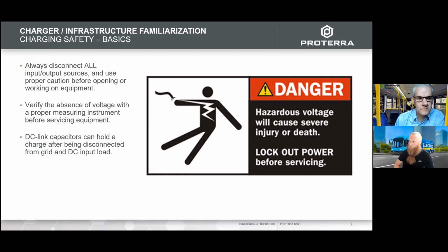For any charging system—whether it's your depot charger, overhead fast charger, or inductive charger—this all requires the same thing: verify the absence of voltage with a proper measurement instrument before servicing the equipment. Test before you touch, as we always emphasize. You also need the right digital multimeter—if it's rated at 400 volts, it's not appropriate for an 800 volt system, so make sure you have the right meter for the task.